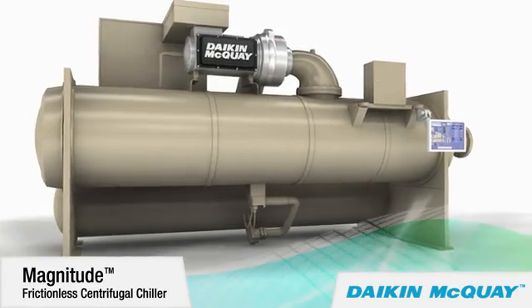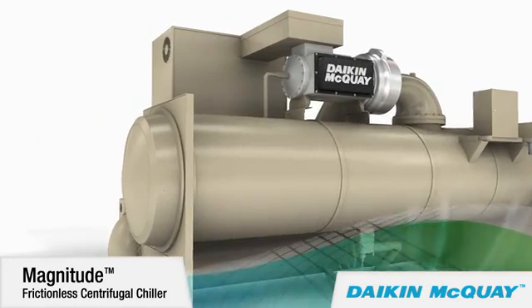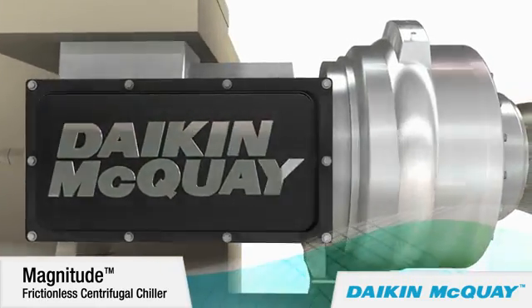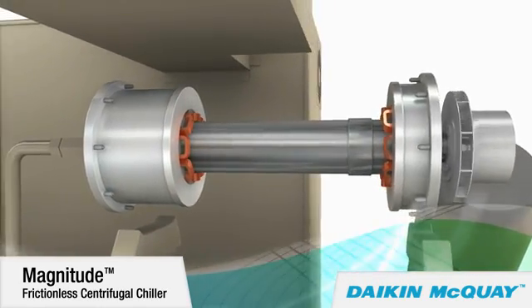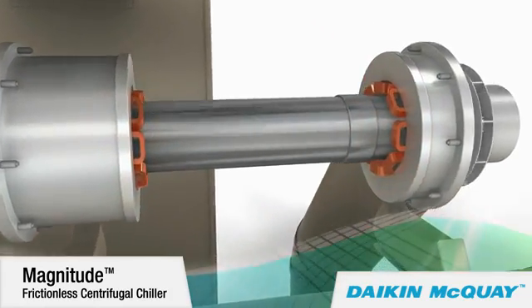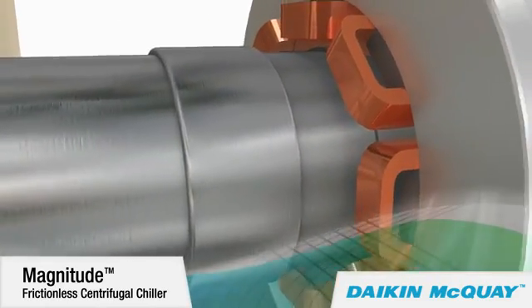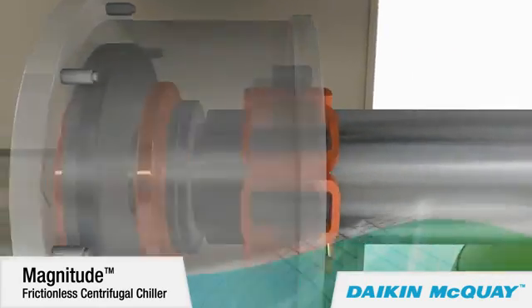Now the next generation of magnitude chillers is available from 400 to 550 tons. The magnitude chiller's exceptional efficiency is a result of the direct drive magnetic bearing compressor technology that eliminates the friction inherent in traditional centrifugal compressors. A digitally controlled magnetic bearing system replaces conventional lubricated bearings, and the direct drive motor eliminates the need for a lubricated gearbox and associated power losses. The frictionless compressor shaft is the compressor's only moving component, and it rotates on a levitated magnetic cushion.